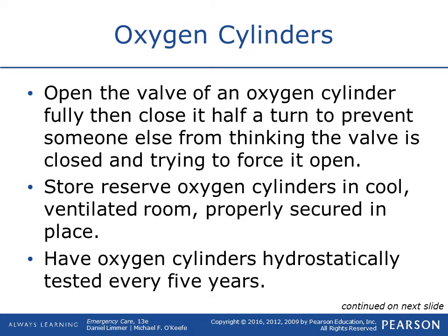Whenever you open up an oxygen cylinder, whether it's your main valve or your portable one, you just want to open them all the way and then go back about half a turn. That way, if you open it all the way and somebody thinks that it's not open and they try to open it, they're going to think it's really stuck and they could potentially break the stem. So if you open it all the way, back just half a turn. If they don't realize it's on and they go to open it, they turn it half a turn and they realize, oh, it's already open.